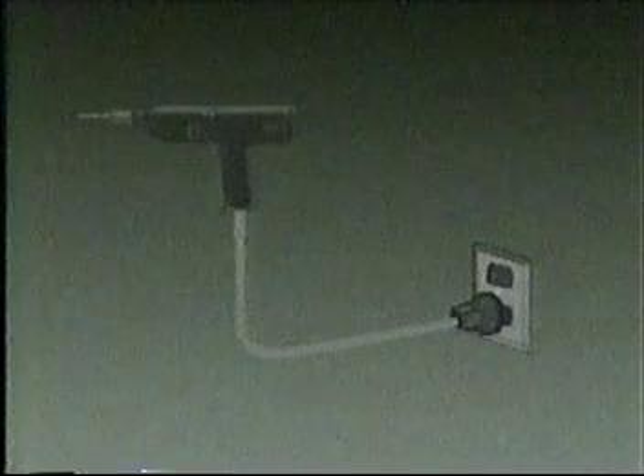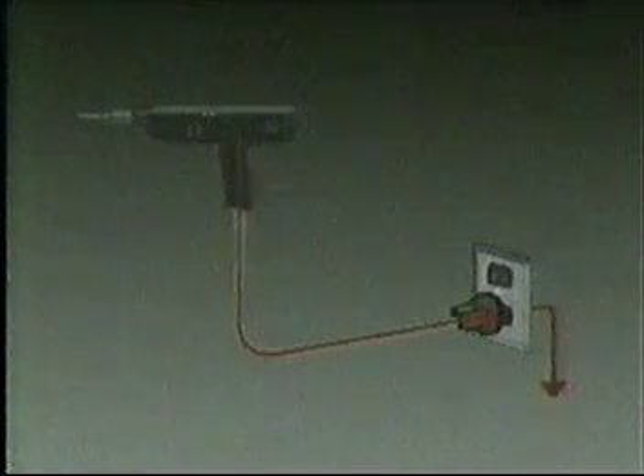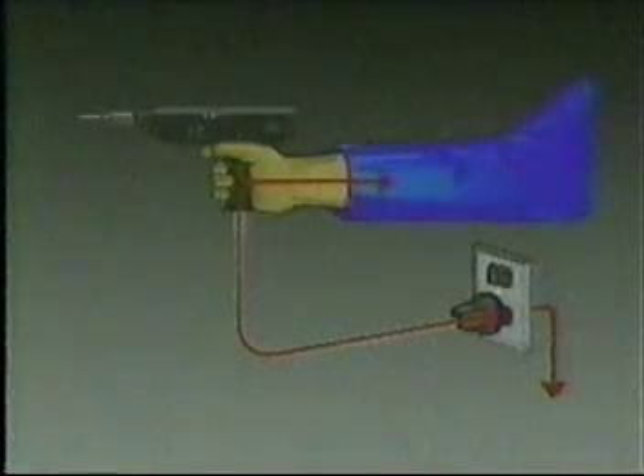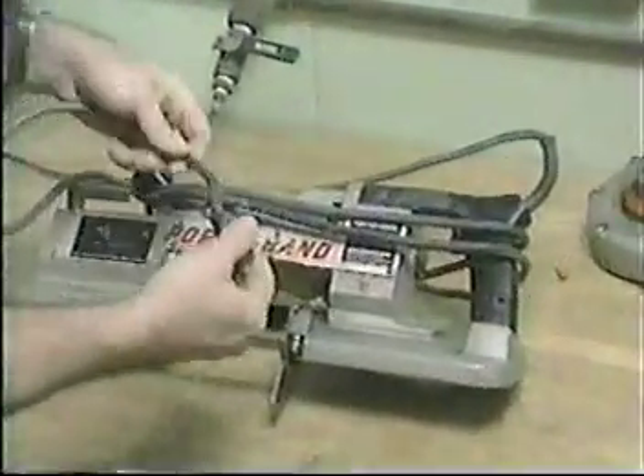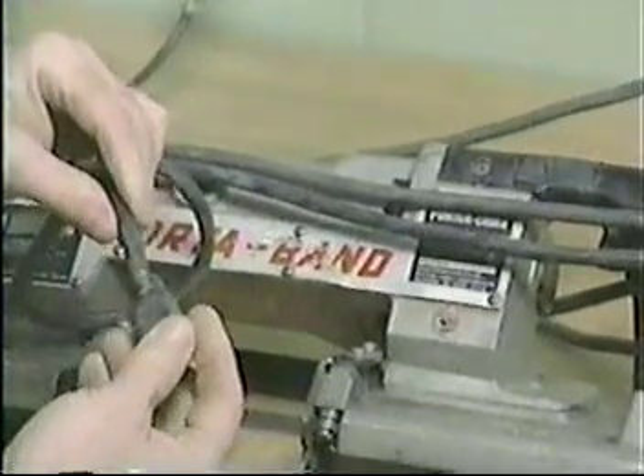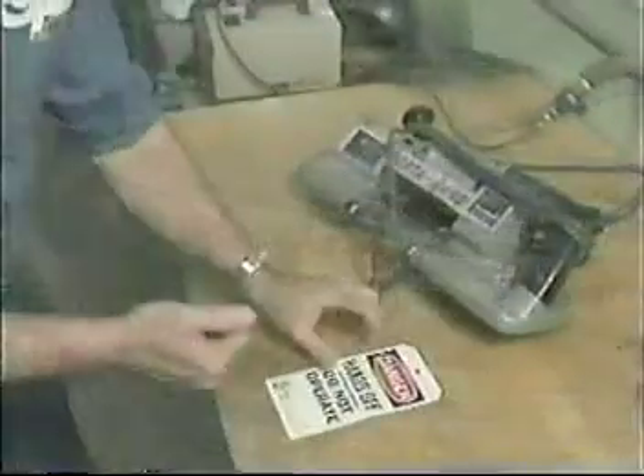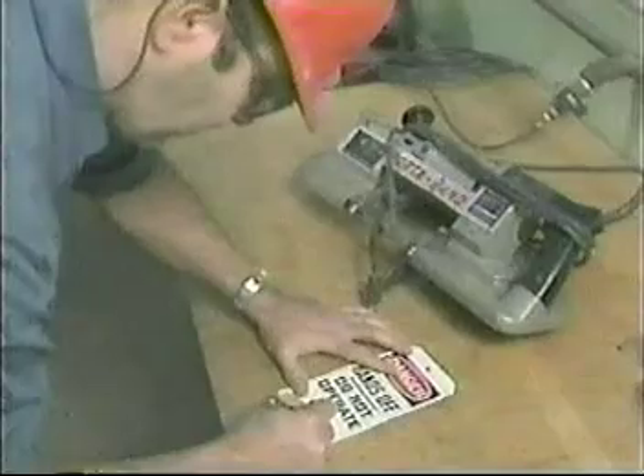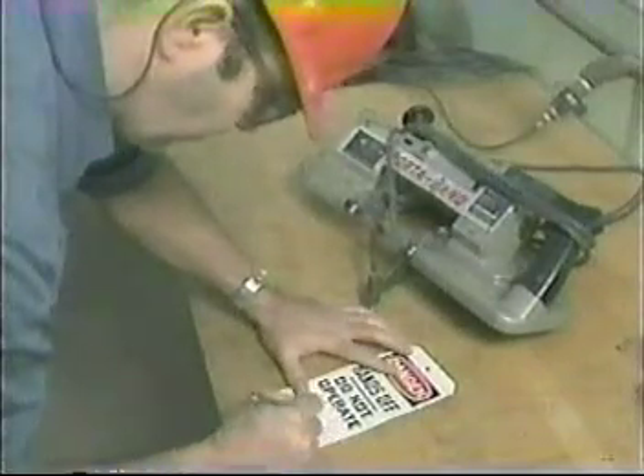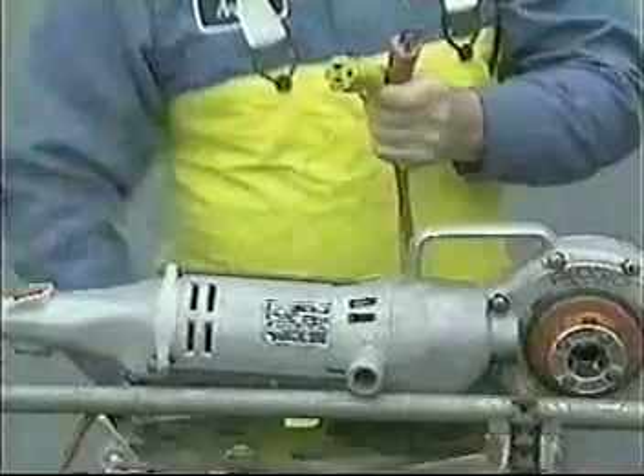One of the most common misconceptions about electrical safety is that regarding safety provided by grounding. It is not foolproof. Current returns to its source through every conductive material available. While most will be dissipated through ground, some will also follow other pathways. Portable equipment should be inspected before each use to ensure that the ground connection is in place, the power cord is in good condition, and the equipment is free of any potentially hazardous conditions or defects.